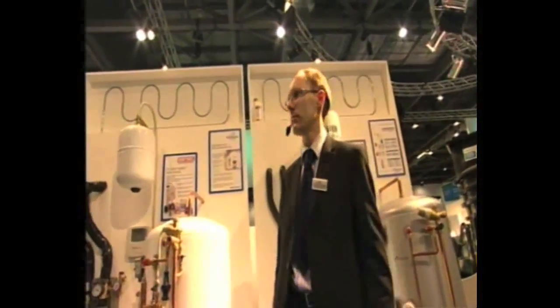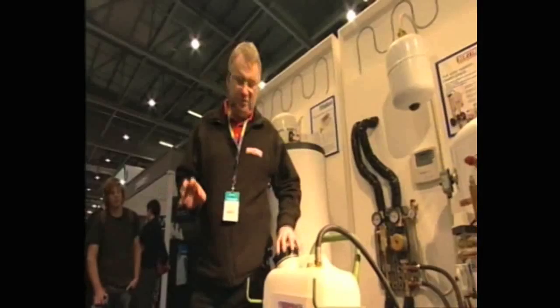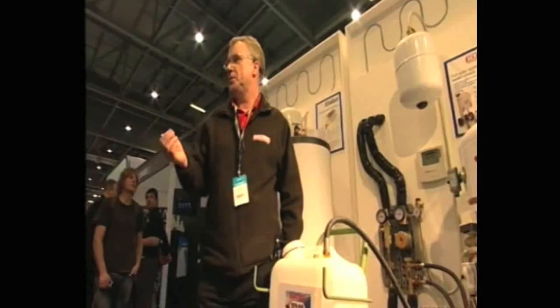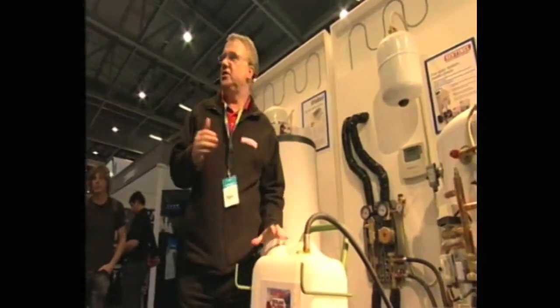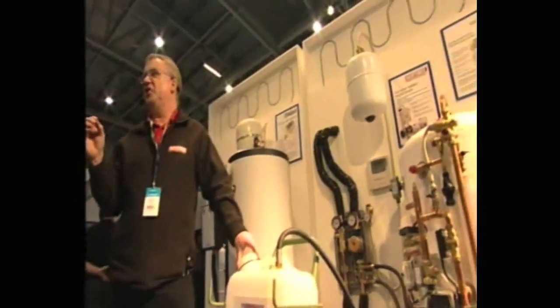Just back onto the maintenance. One of the questions that comes up is how you tell if the glycol has degraded. Well, over a period of time, the glycol will degrade with age. And you can tell by, you lose the frost protection. So you can use a refractometer to test for the frost protection. So you can measure whether it's still got the same protection you had at the beginning. It changes color. It tends to go darker.